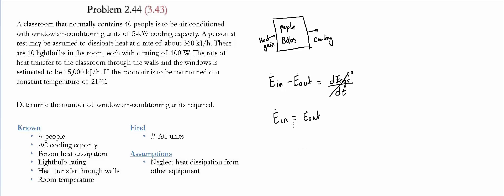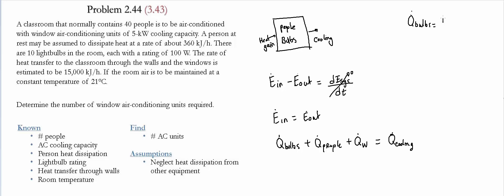The rate of energy in equals the rate given by the bulbs plus the rate given by the people plus the heat gained through the walls. What leaves is the rate of cooling. For the bulbs: there are 10 bulbs, each dissipating at 100 watts, so the total rate is 1 kilowatt.